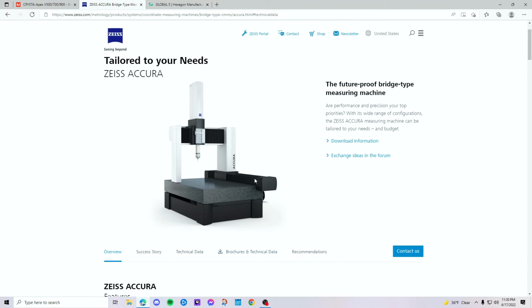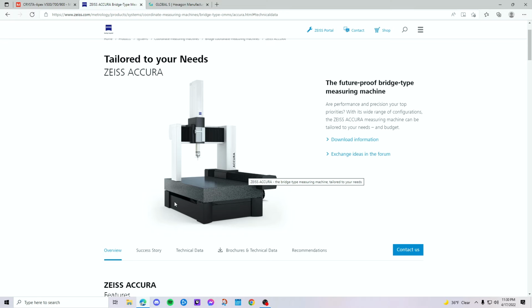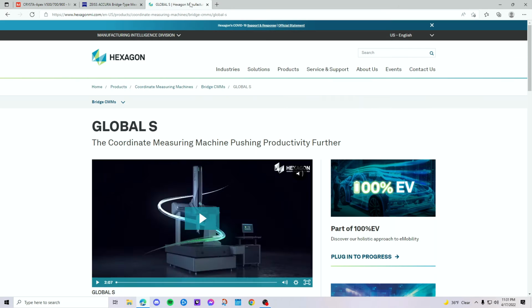The different thing about Zeiss compared to others is they tend to use what is known as a fixed probe system. With some, you can get a rotational probe similar to a Renishaw PH10, called the RDS, which is fantastic and it's great for multi-angles. But Zeiss machines are a fantastic CMM, and they run a software, generally speaking, called Calypso. Calypso is one of the two most common softwares that are found, and it's my personal favorite software to program in.